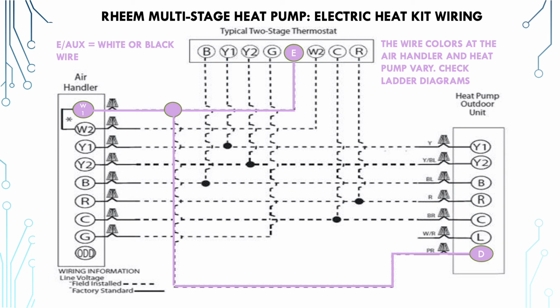Now, the wiring for this, when you see this, you've got on the heat pump, Rheem has the letter D represented on the board for defrost. Your actual terminal label can vary from one brand to another. Not everybody calls it that. I see the letter L used sometimes. Either way, when defrost is called for, it needs a way to turn on the electric heat while it's defrosting, because defrost, in a sense, is just the heat pump shutting off the condenser fan motor and it shifts the reversing valve into cooling mode. So now it's taking heat out of the home to the unit to help thaw it out because it's getting all frosty. And while it does that, it turns on electric heat to offset the cold air that it's generating.